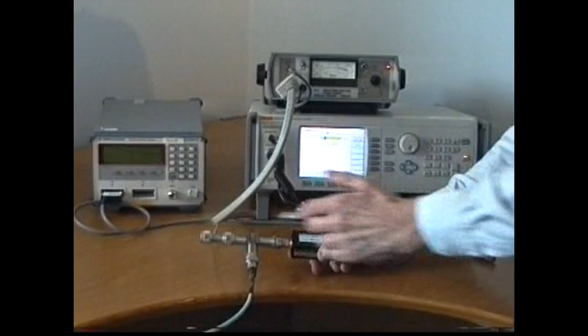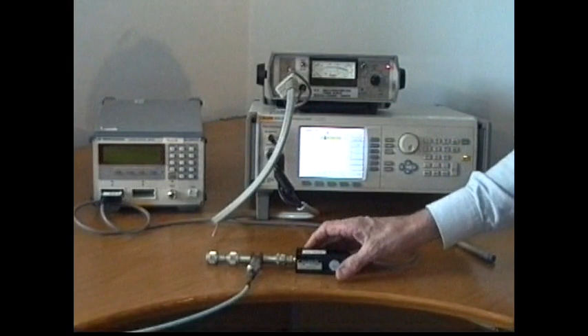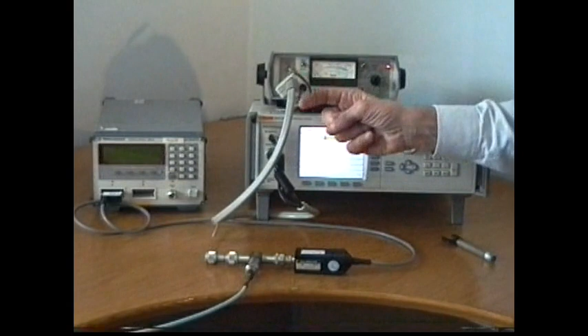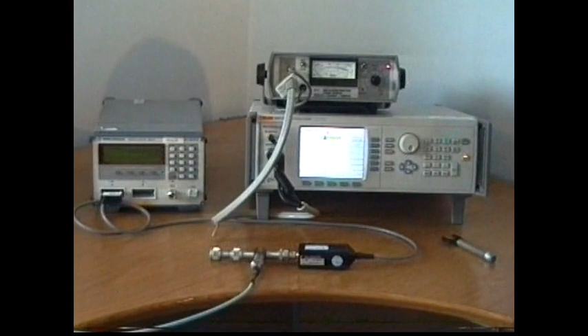Now this involves some metrology to account for the splitter tracking and loss errors, and also to convert from what is probably a measurement on the power meter of power rather than voltage, unless you happen to be lucky enough to have a power meter that can respond in terms of voltage as well as power. However, in the case of the 9640, we will see that process is much simpler. We have a signal delivered directly to the input of the unit under test from the 9640 leveling head, much simpler connections, and we could also select the output of the 9640 to be directly displayed in terms of voltage.